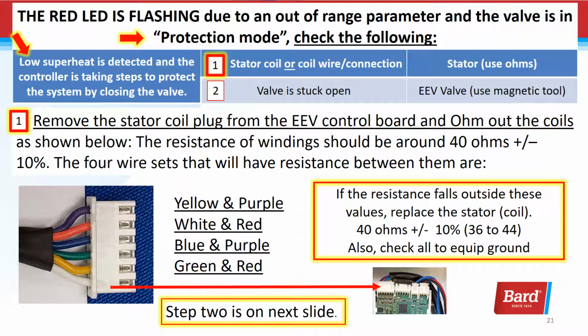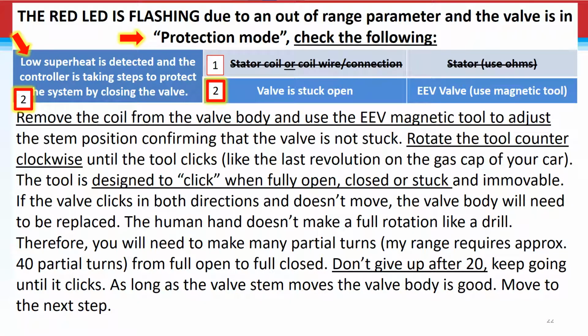Remove the stator coil plug from the EEV control board and ohm out the coils as shown below. The resistance of the windings should be around 40 ohms plus or minus 10%. So the 4 sets that will have resistance are listed: yellow, purple, white, red, blue and purple, and green and red. If your resistance falls outside these values, replace the stator coil. So 40 plus or minus 10% is 36 to 44, where all your measurements are going to fall. And also, check all equipment to ground. Now that we know the coil is okay, let's check the valve out, see if it's stuck in a position.